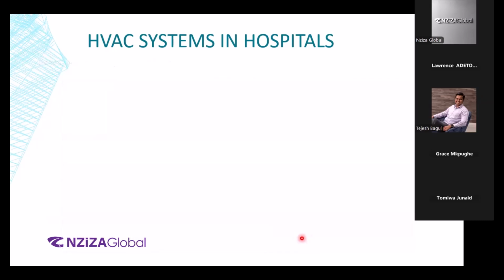All right. So now let's focus on the first one, that is the constant air volume system. Okay. Again, the constant air volume systems will be divided as single duct, the first one, with terminal heat. What does this mean? The duct going out of the air handler will be just one. Okay. That duct will be connected to individual ducts serving the areas. And in that duct, you will have a reheat. Okay. So the temperature out of the air handling unit might be somewhere around 15 to 16 degrees centigrade. And then you will raise it or lower it, raise it because we are trying to use terminal heat. You will raise it to maintain what the supply air temperature requires to be at the zone. Okay. So that will be the entering air temperature into the room.